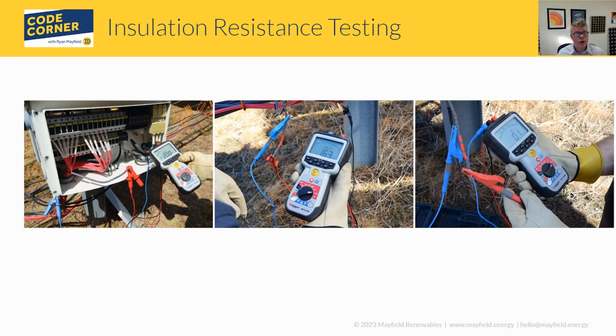The next one over in the middle, you see 16.3. That is a relatively low reading, whether that's megaohms or kilohms, I forget because I can't see that screen very well. Nonetheless, it's lower. And then on the far right, you see 0.1. All of these readings should mean something to you when you've gone through the proper training and understand what you're looking at, in terms of the relative health of those conductors. The one in the middle would be the biggest one to take pause and look at and say, there might be something wrong here.